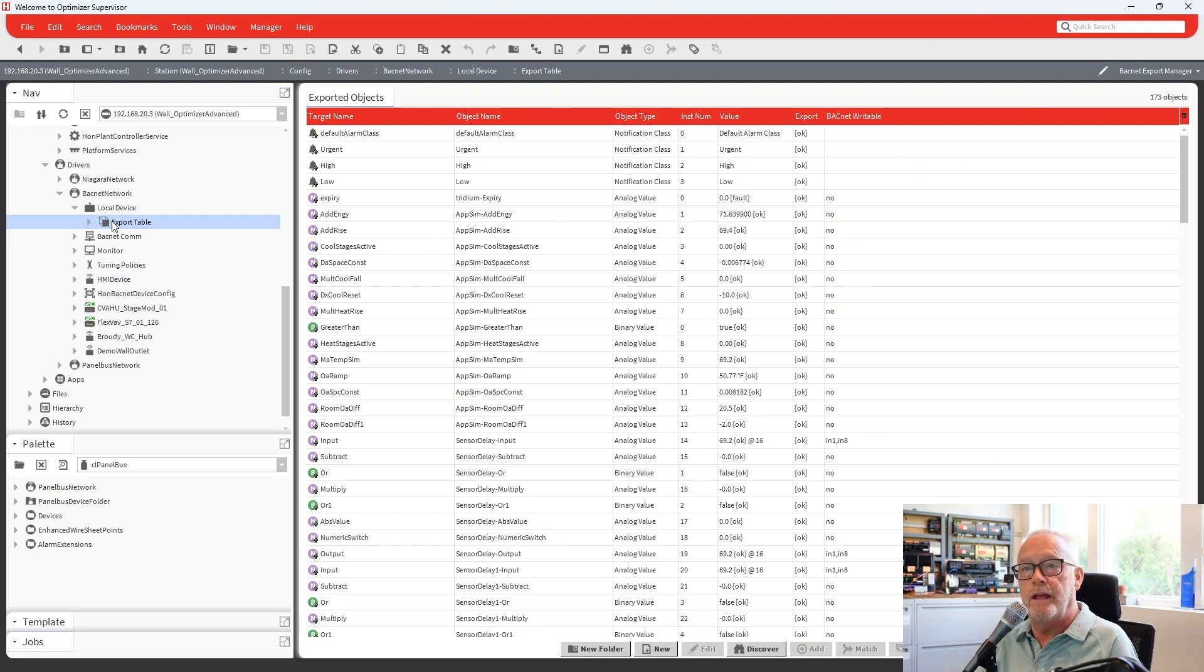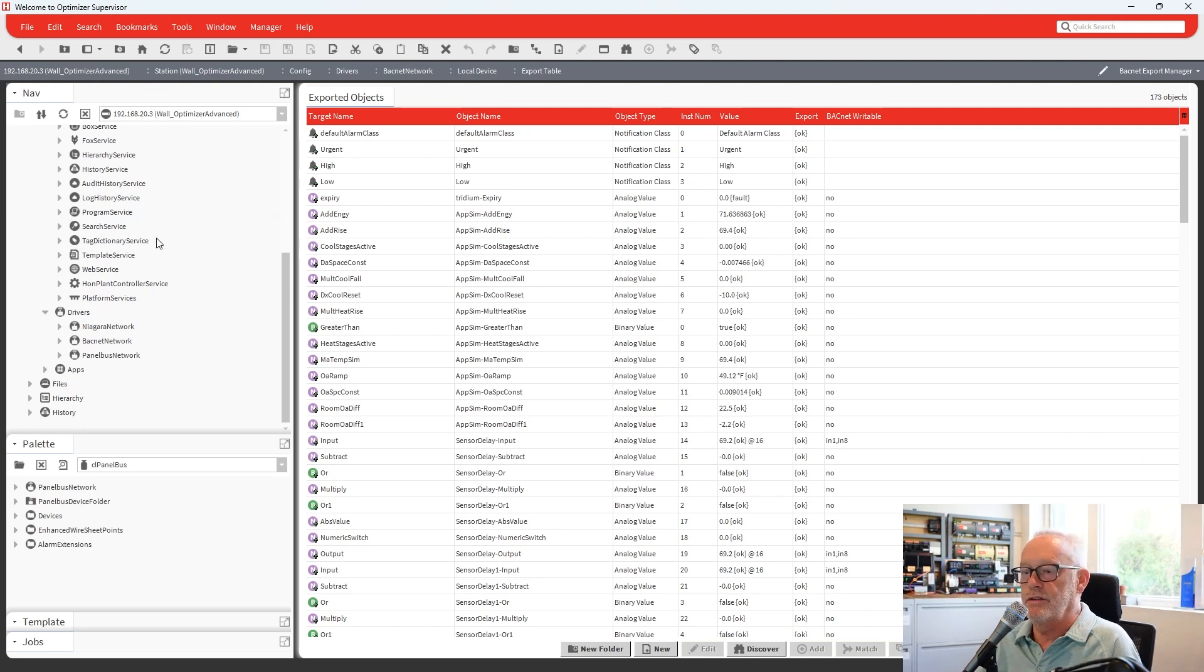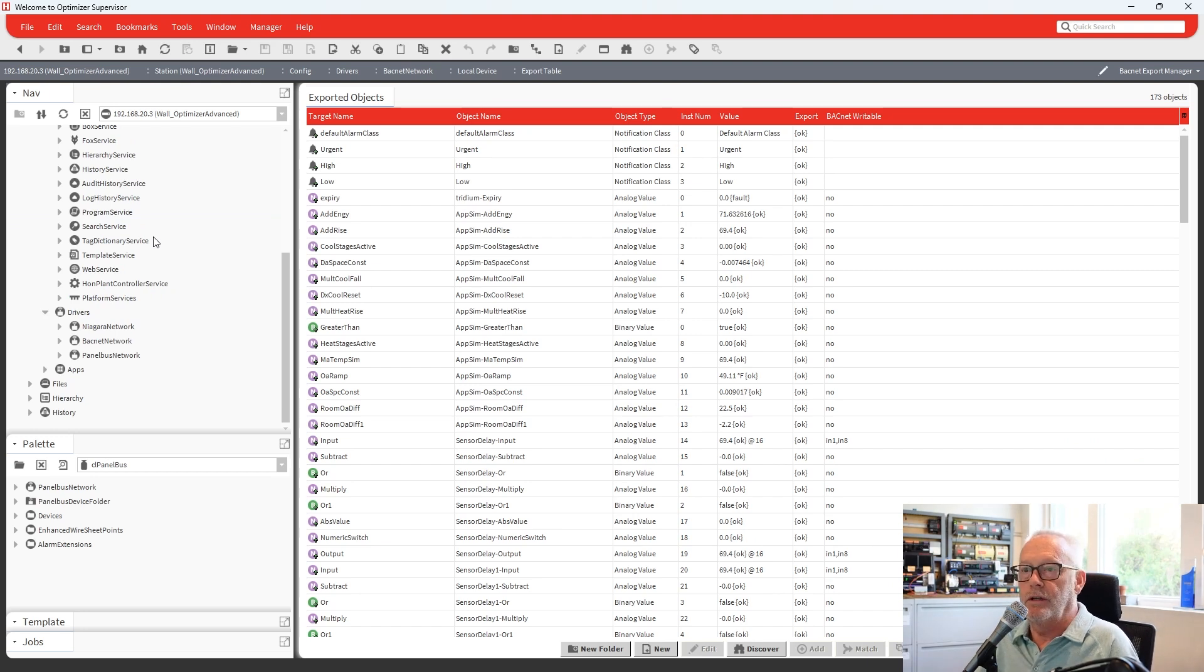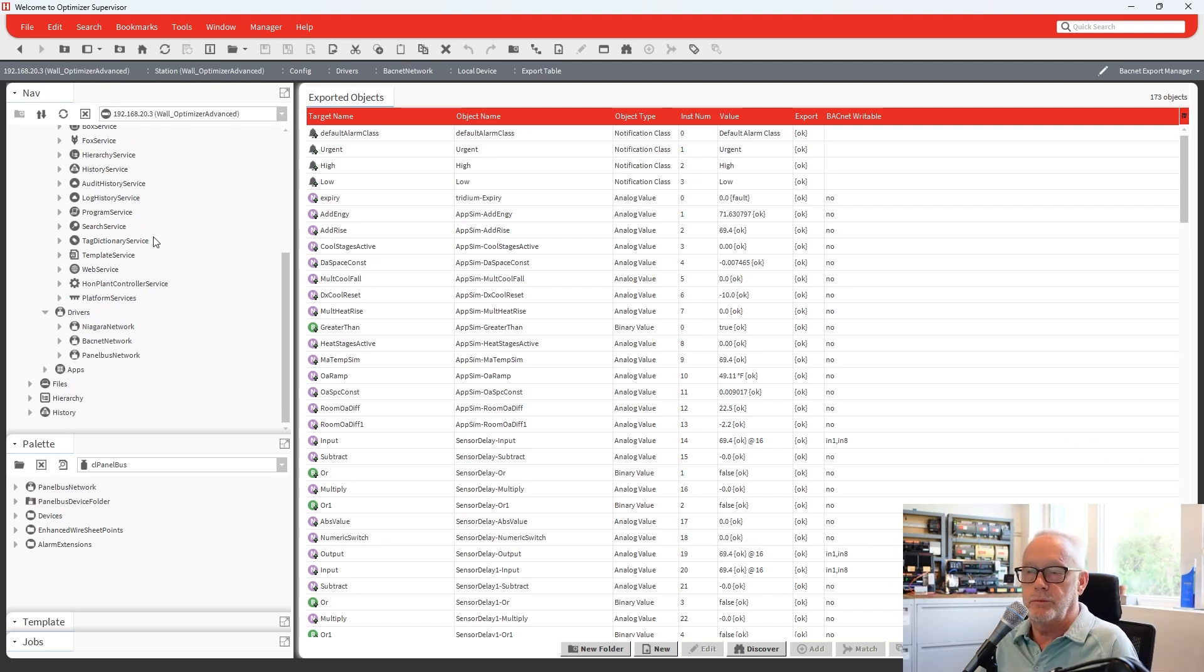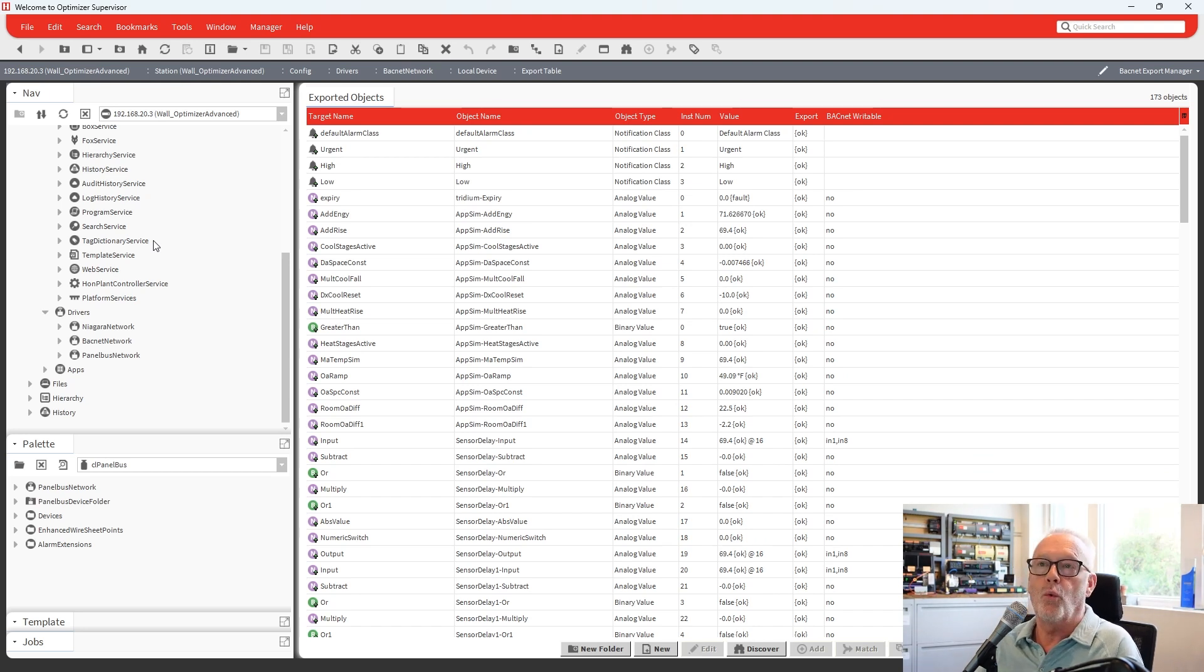And then recently, Honeywell came out with version 4.14.0, their optimizer software. And if you were to go and upgrade this station from 4.13, which is what I was running, if you upgrade this to 4.14, it will break the HMI and it will no longer work.